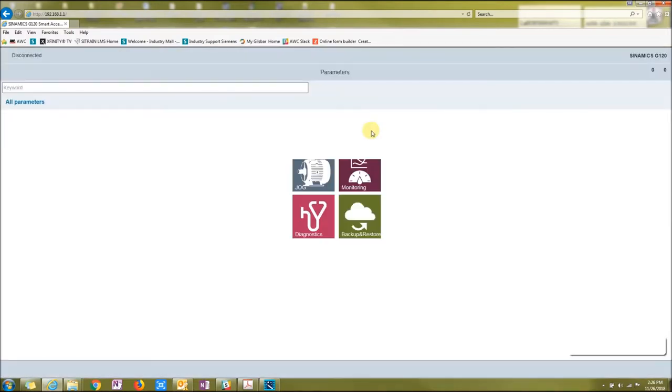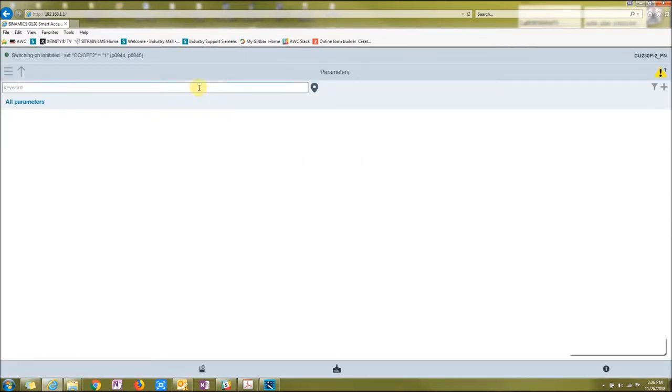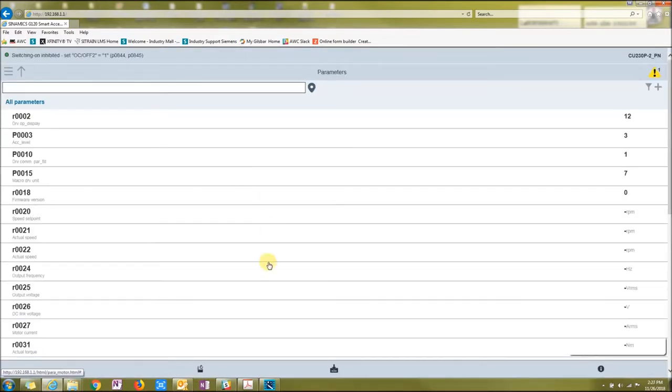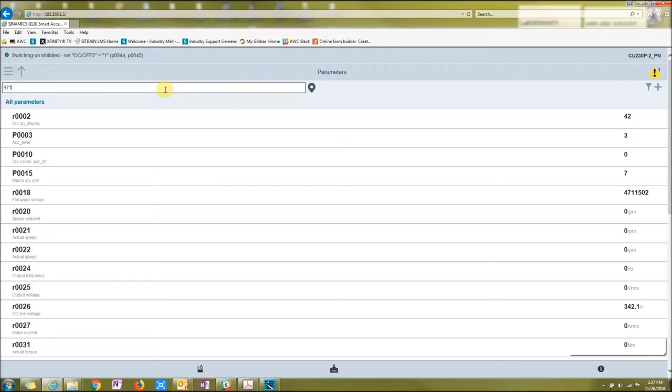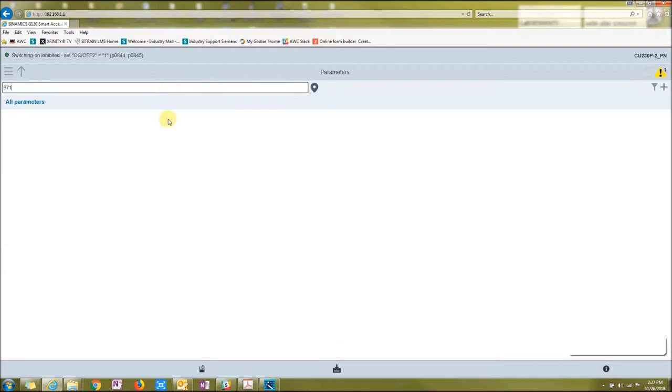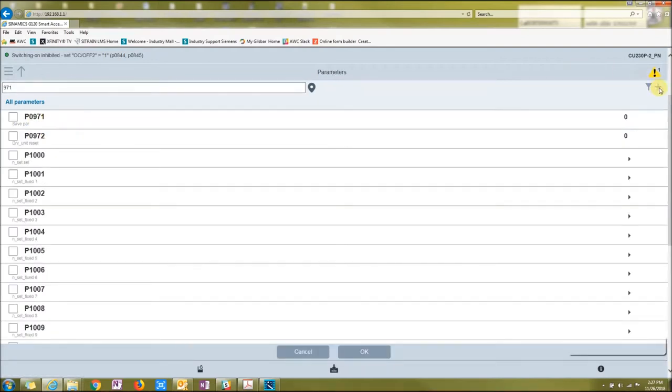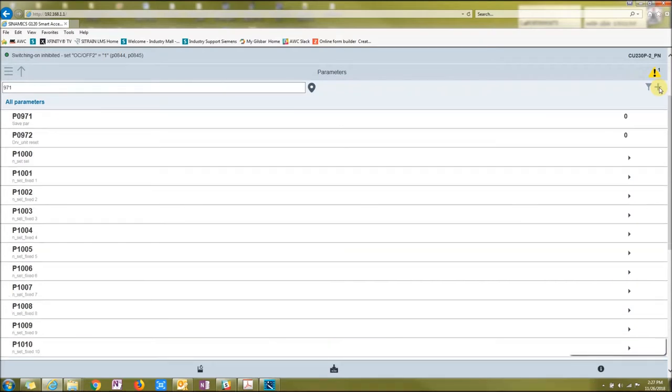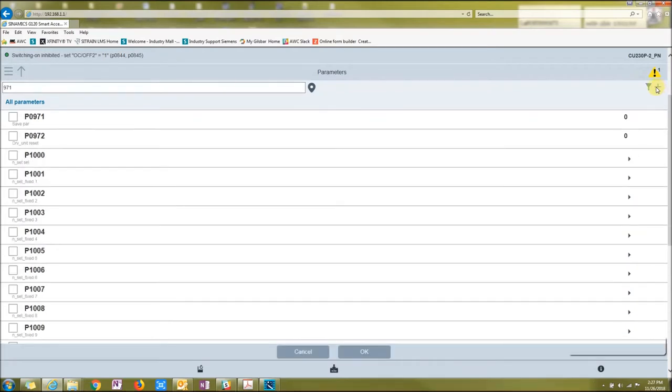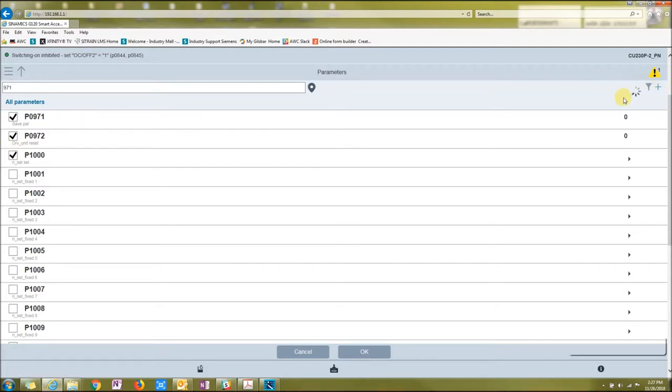You can go to your parameter view and look at all your parameters. Or say if you want to just... you know a certain parameter, like 971 is our save parameter. So 971, which is our RAM to ROM, press enter. You can go straight to it. Or you can filter it.